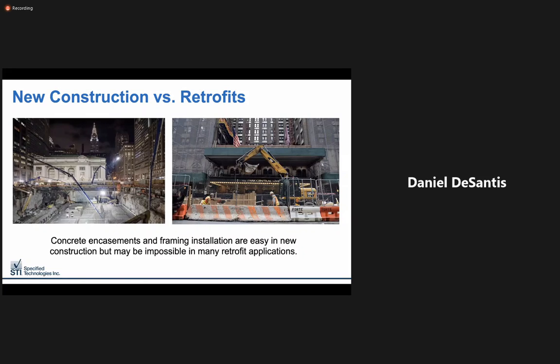Structures like parking garages and stadiums also have their circuit integrity needs. Traditional means of shaft enclosure may not fit the aesthetic of a particular building, especially those with an open ceiling or industrial design concept. Endothermic wrap, as well as providing the required 2-hour rated enclosure for critical path services, blends into the surrounding mechanicals as well. It can be jacketed with a colored PVC to fit the desired aesthetic of the project as well.